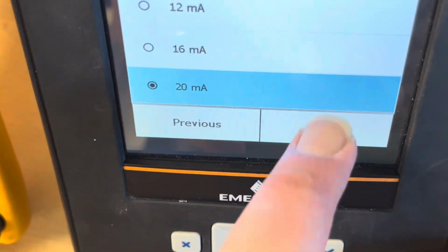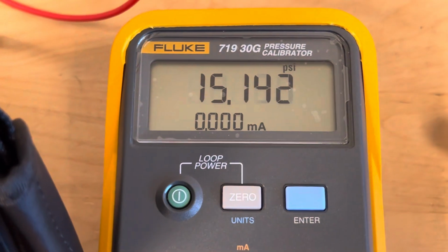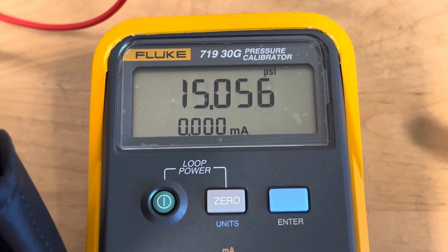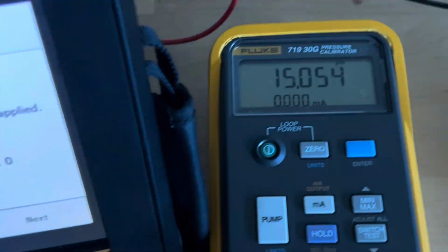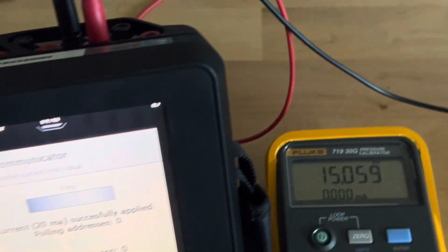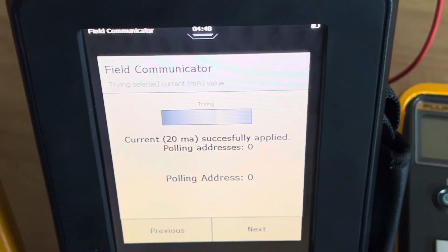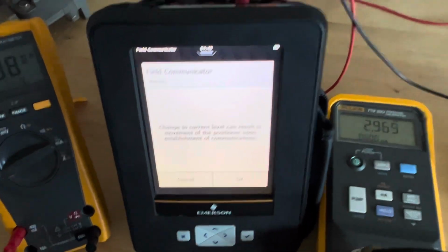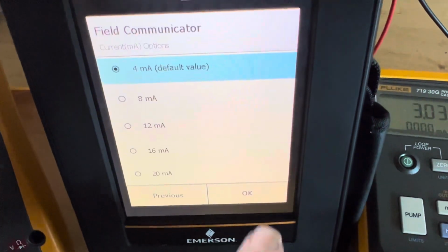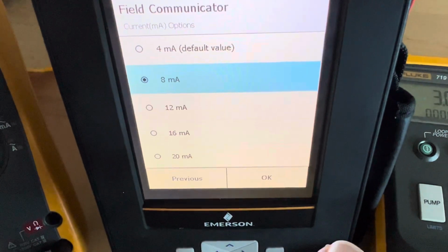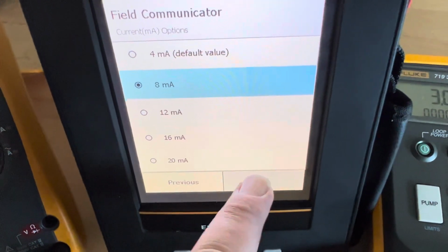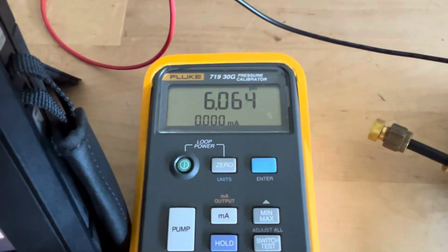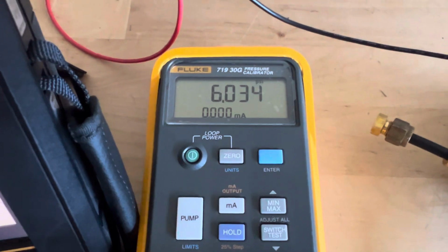Now it looks pretty good. 3.0 at 4 milliamps. Let's try our 20 milliamps. We'll select 20 milliamps, we select OK, and we're at 15.0. That's good enough. All right, now we're going to walk through our other PSI levels. So I'm going to hit previous. I'm going to hit OK. I'm going to hit 8 milliamps, which should give me about 6 PSI. Oh, dead on. It looks real good, 6.0.